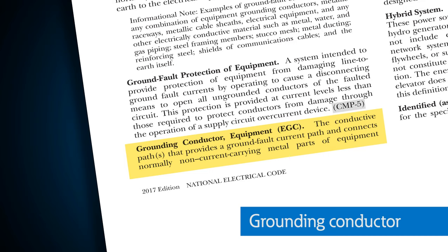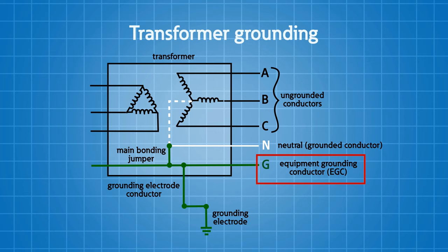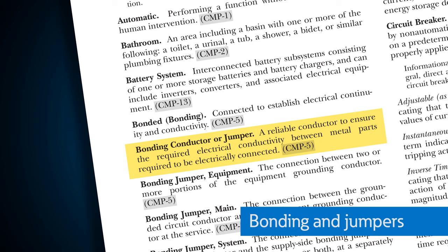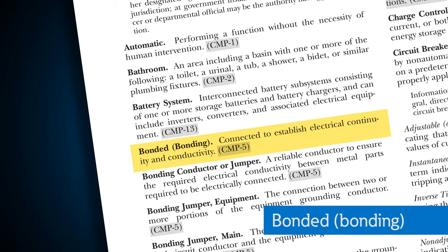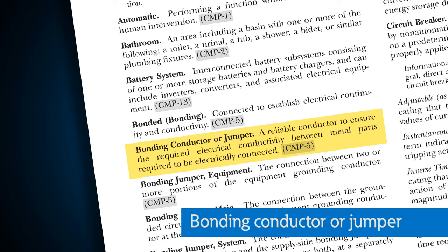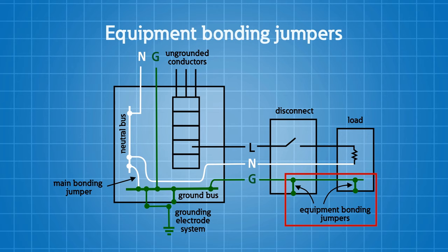Now the grounding conductor — that's a conductor used to connect the equipment or the grounded circuit of a wiring system to a grounding electrode or to the grounding electrode system. Now bonding and jumpers: bonding is defined by the NEC as connected to establish electrical continuity and conductivity. This is a very important term as we work throughout the power distribution system. Bonding conductors, or jumpers, are reliable conductors that ensure the required electrical conductivity between metal parts required to be electrically connected together.